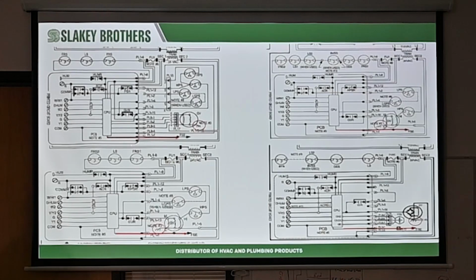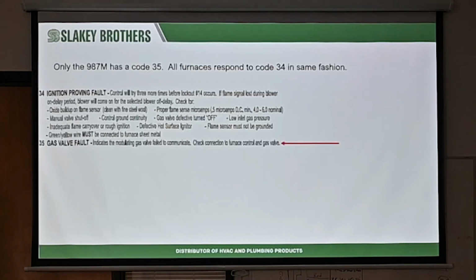Ground wire on the gas valve, real important as well. First, the other major thing for sensing a flame. The green, yellow wire must be connected to the furnace sheet metal. Your gas valve needs to be grounded. Not so much that, but you have to have a good ground from the home. The home has to have a good ground for your appliance plug, whatever you're using. Your furnace has to have a good ground. If your furnace ground is faulty, your flame proving will be affected. It won't sense a flame that easily, and you'll have a problem.